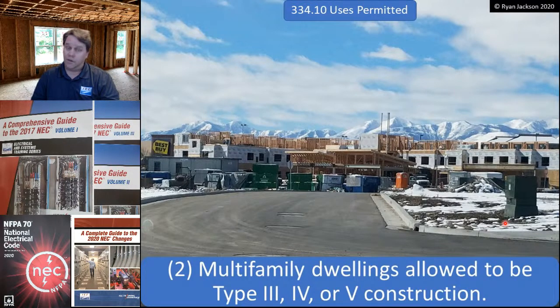nobody adopts. And I mean that quite literally, nobody adopts it. So I'd go off of the IBC. That's what everybody in the United States adopts, the International Building Code. So that's what I go off of. And I'll explain what 3, 4, and 5 are in just a minute. But for multifamily dwellings, apartments, townhouses, if you're allowed to build them out of type 3, 4, or 5, then you can use NM cable.